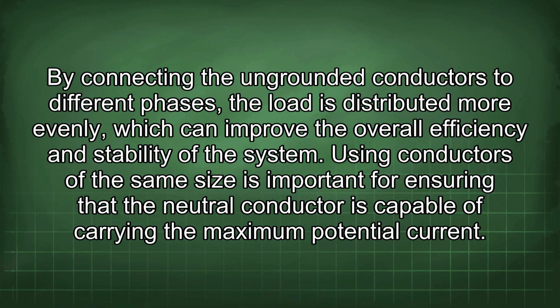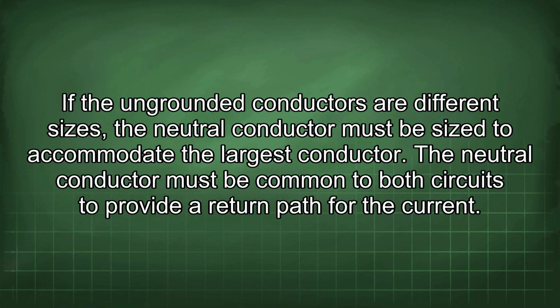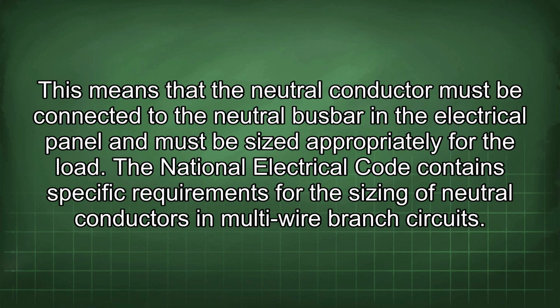Using conductors of the same size is important for ensuring that the neutral conductor is capable of carrying the maximum potential current. If the ungrounded conductors are different sizes, the neutral conductor must be sized to accommodate the largest conductor. The neutral conductor must be common to both circuits to provide a return path for the current. This means that the neutral conductor must be connected to the neutral busbar in the electrical panel and must be sized appropriately for the load. The National Electrical Code contains specific requirements for the sizing of neutral conductors in multi-wire branch circuits.